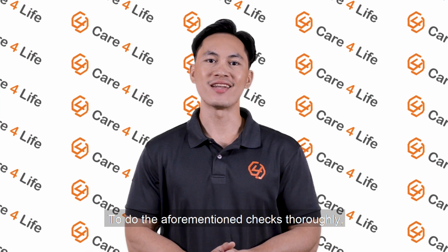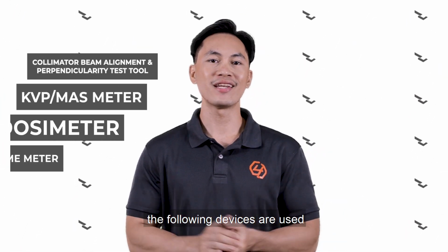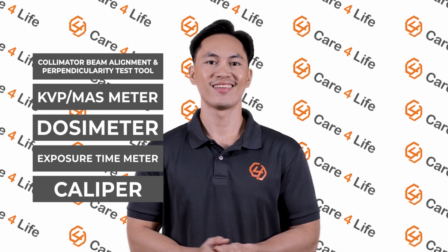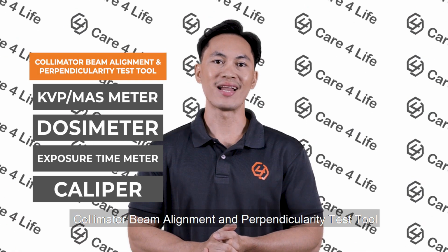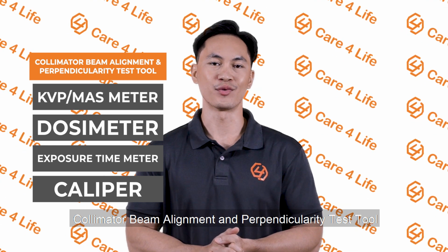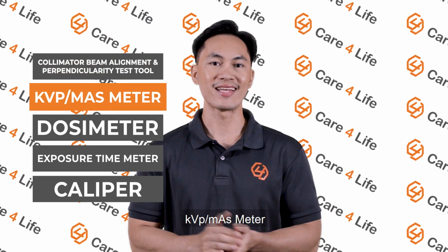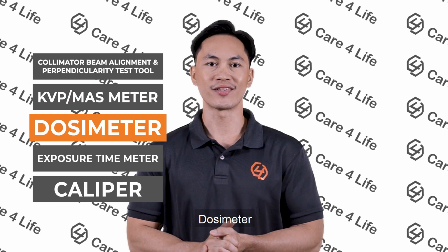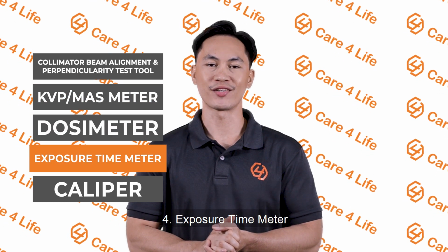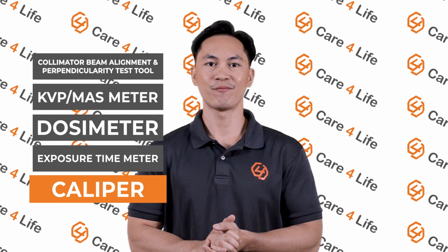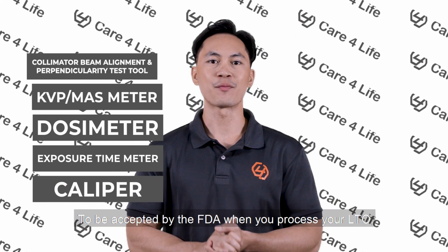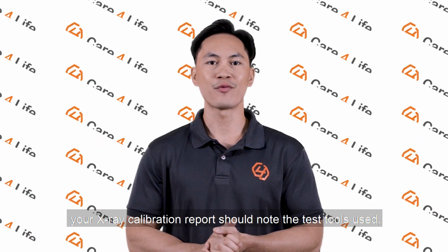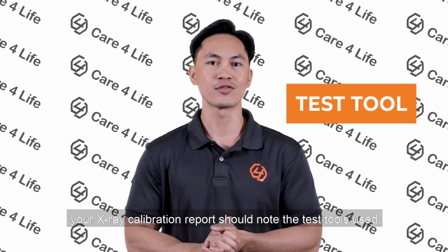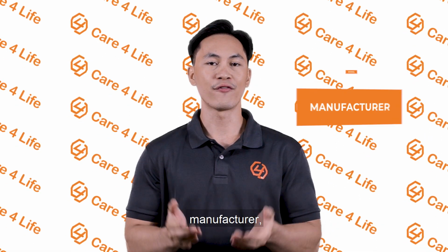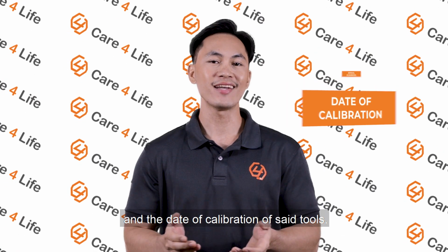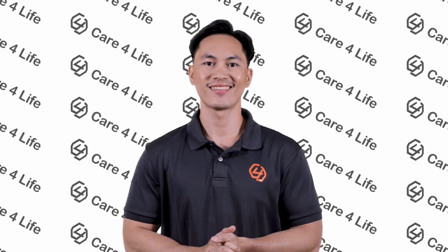To do the aforementioned checks thoroughly, the following devices are used. Number 1. Collimator beam alignment and perpendicularity test tool. 2. KVP and MAS meter. 3. Dosimeter. 4. Exposure time meter. 5. Caliper. To be accepted by the FDA when you process your LTO, your X-ray calibration report should note the test tools used, including the model, manufacturer, serial numbers, and the date of calibration of said tools.